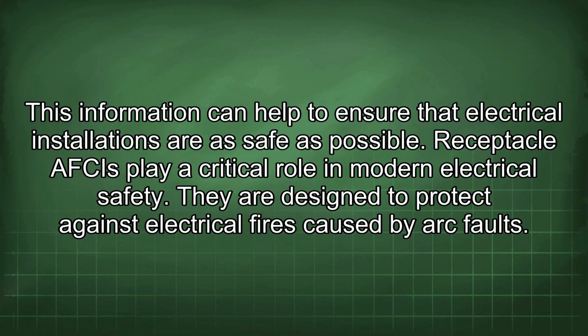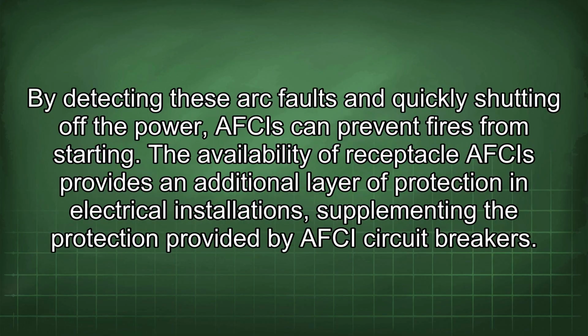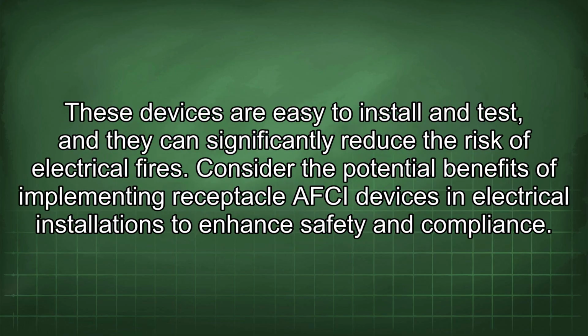Receptacle AFCIs play a critical role in modern electrical safety. They are designed to protect against electrical fires caused by arc faults. By detecting these arc faults and quickly shutting off the power, AFCIs can prevent fires from starting. The availability of receptacle AFCIs provides an additional layer of protection in electrical installations, supplementing the protection provided by AFCI circuit breakers. These devices are easy to install and test, and they can significantly reduce the risk of electrical fires.